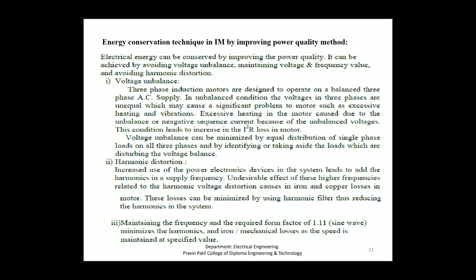The second one is harmonic distortion. The use of power electronic devices in the system leads to the addition of harmonics to the supply frequency. The undesirable effect of these higher frequencies related to the harmonic voltage distortion causes iron and copper losses in the motor. These losses can be minimized by using a harmonic filter, thus reducing the harmonics in the system.